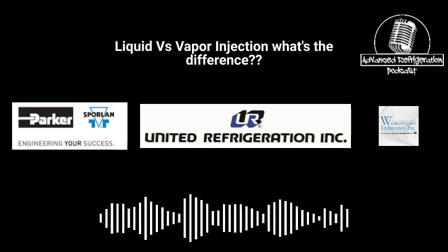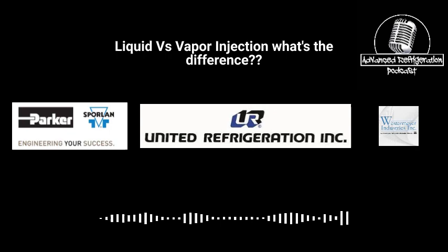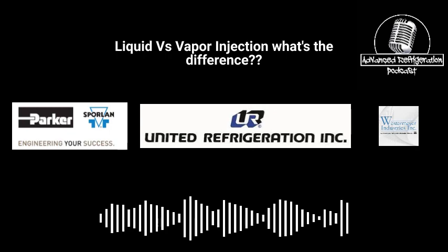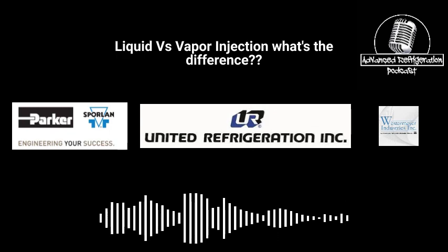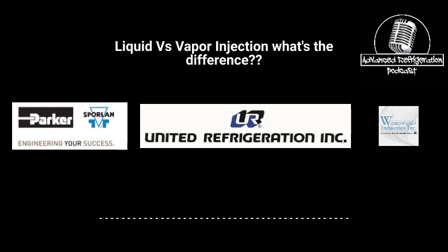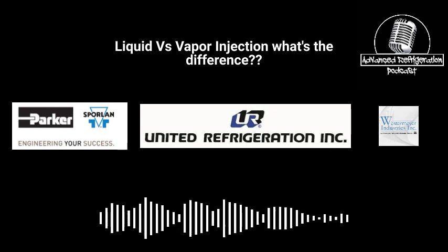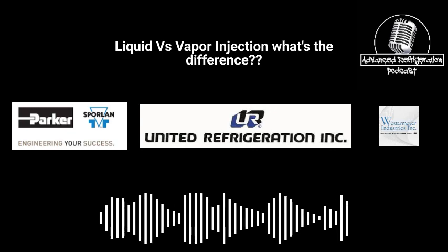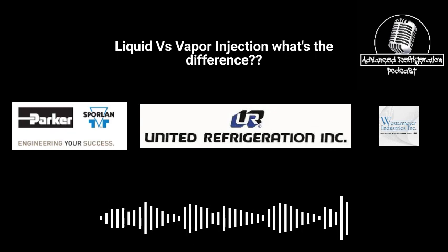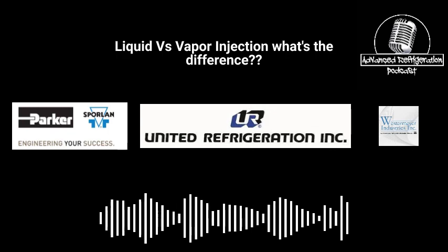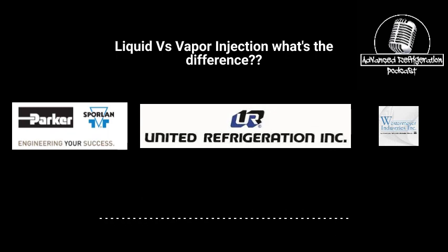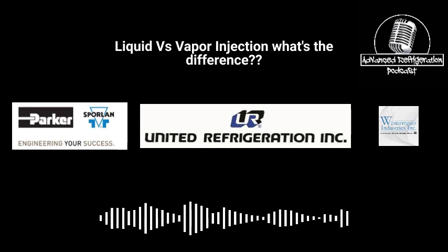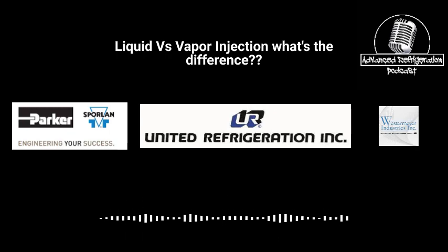So the other thing with the Y10 valves. I'm a big proponent, and I see a lot of Bitzers the same way. They'll say it's a 220, or is it a, for the Y valve? It's 190, 210, and 230 typically. I see a lot of 230 valves. I want nothing to do with a 230 valve. Personally, if I'm replacing it, I'm probably putting a 195 in. 190, they don't make 195. 190, I'm putting in the lower one.